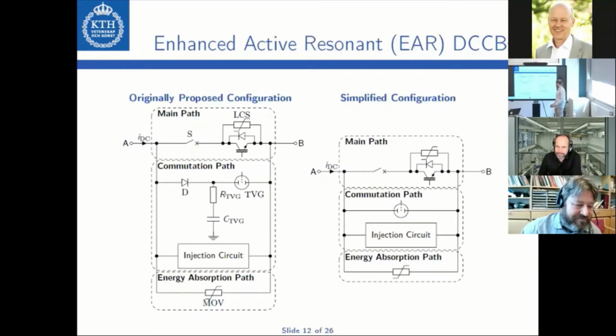I mean, this is very implementation dependent. But one thing is that the DCCB has to be aware of the operating current when one wants to utilize this proactive commutation mode, because then the DC breaker has to decide at this current level, for instance, using a threshold. The other thing that has to be monitored is the voltage. I have not put too much emphasis on where one would have to measure, whether across the triggered vacuum gap or across the LCS, because in this state it is still basically in parallel when the mechanical switch is open. So possibly one could just measure it across the LCS, maybe easier, and then also avoid the high voltage in the other operation state.